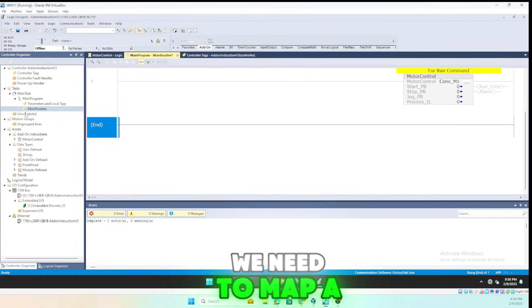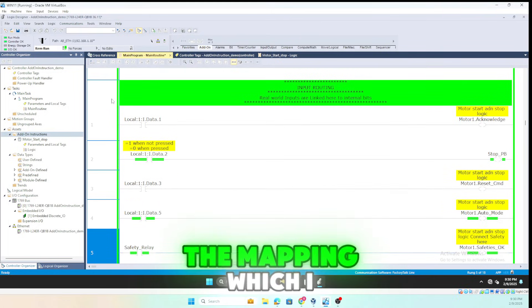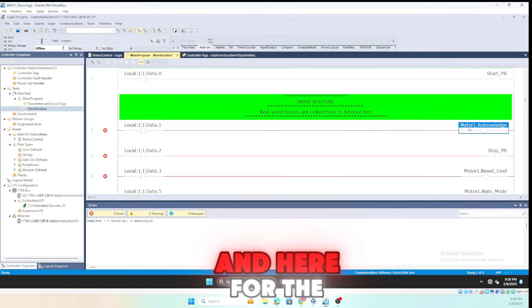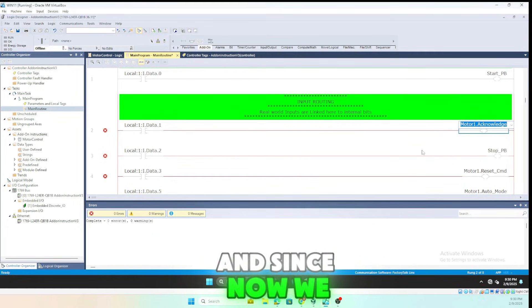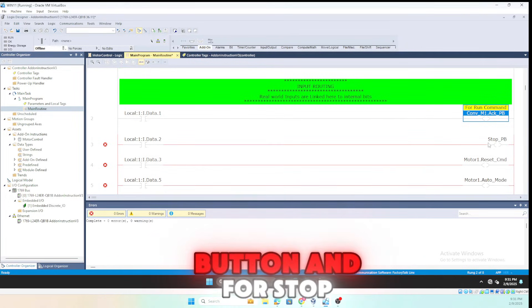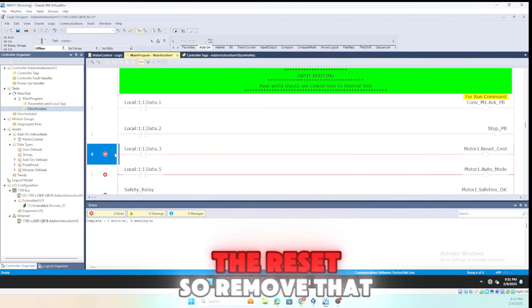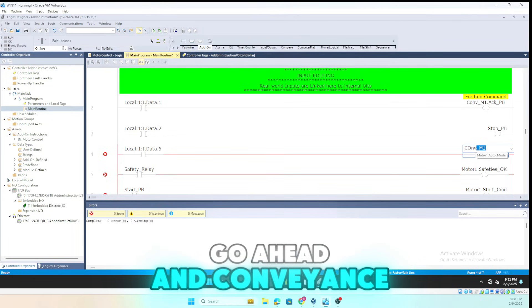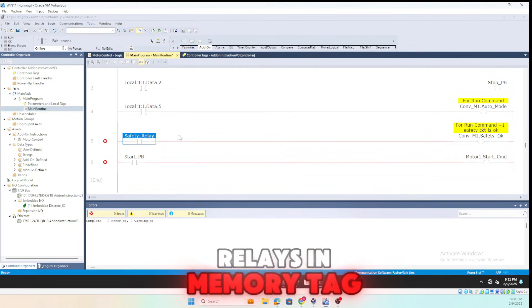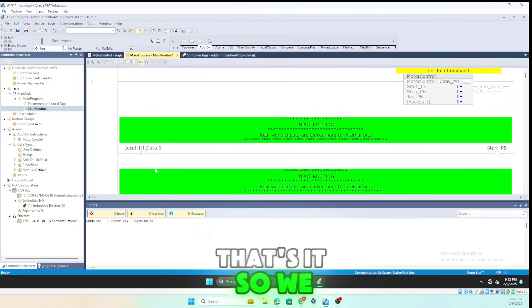Now we need to map inputs and outputs to the AOI. We map a start push button, and for the acknowledge button we use the conveyance M1 instance with dot notation — Conveyance_M1.acknowledge_push_button. For stop push button we create a new stop_pb tag. For auto mode we wire Conveyance_M1.auto_mode, and for safety we wire Conveyance_M1.safety, which is a memory tag. For the start push button we wire it to the main start_pb. All add-on instruction set mappings are now complete.